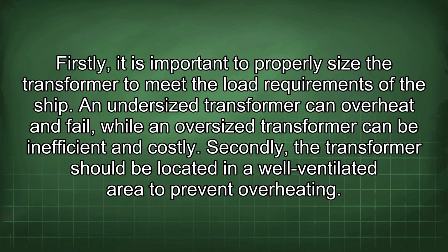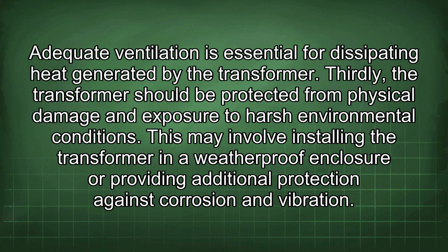Firstly, it is important to properly size the transformer to meet the load requirements of the ship. An undersized transformer can overheat and fail, while an oversized transformer can be inefficient and costly. Secondly, the transformer should be located in a well-ventilated area to prevent overheating. Adequate ventilation is essential for dissipating heat generated by the transformer. Thirdly, the transformer should be protected from physical damage and exposure to harsh environmental conditions. This may involve installing the transformer in a weatherproof enclosure or providing additional protection against corrosion and vibration.